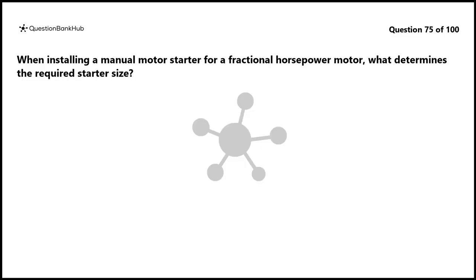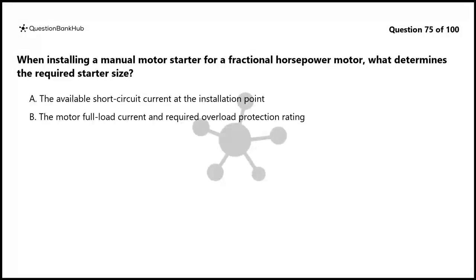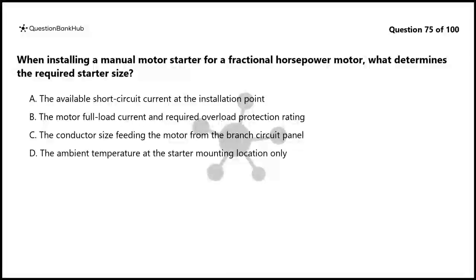Question 75. When installing a manual motor starter for a fractional horsepower motor, what determines the required starter size? A. The available short-circuit current at the installation point. B. The motor full load current and required overload protection rating. C. The conductor size feeding the motor from the branch circuit panel. D. The ambient temperature at the starter mounting location only.